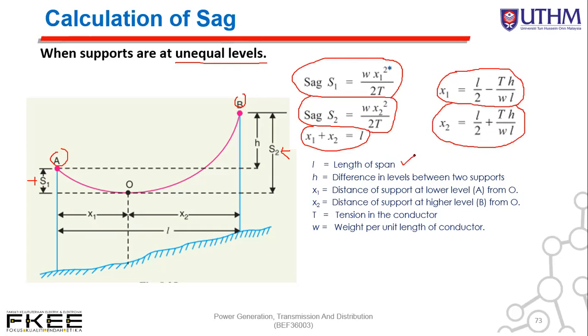L is length of span, H is the difference in level between the two supports. Okay, X1 is the distance of the support at lower level A from O, X2 is the distance of B from O, T is the tension of the conductor, W is the weight per unit length of the conductor.